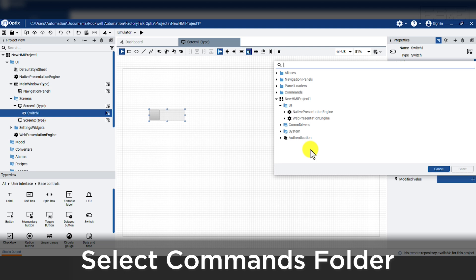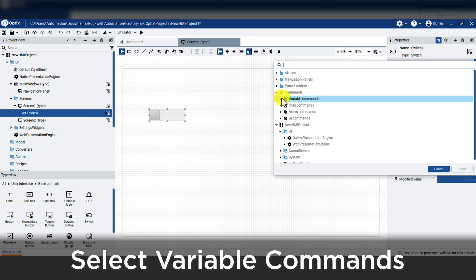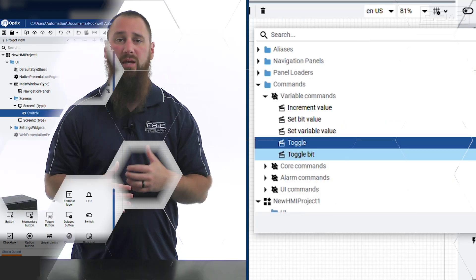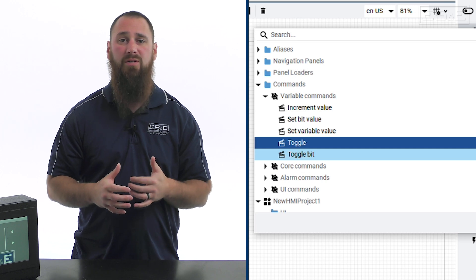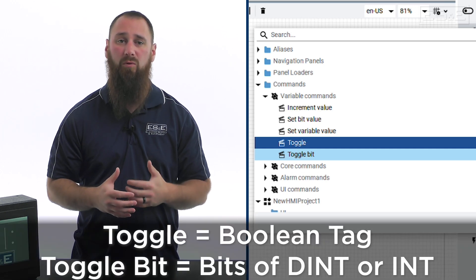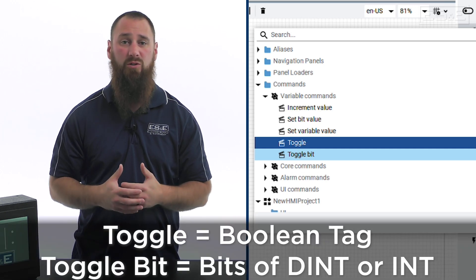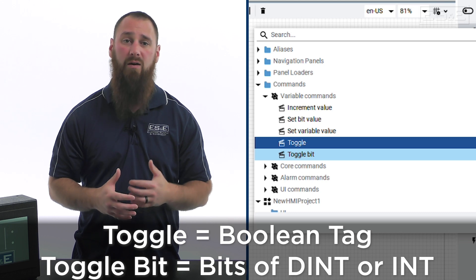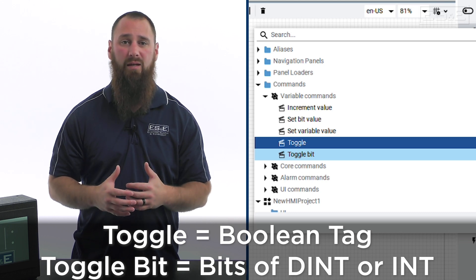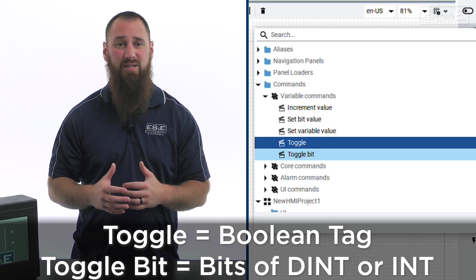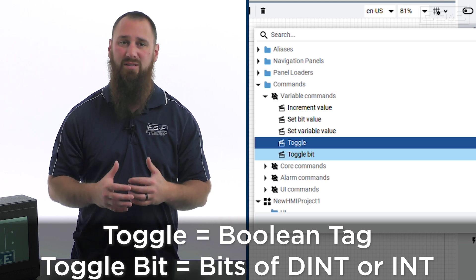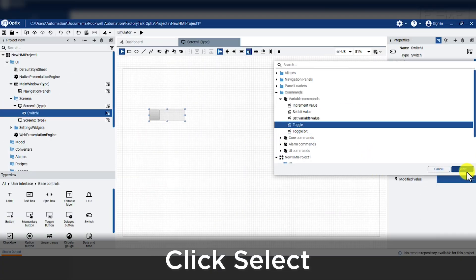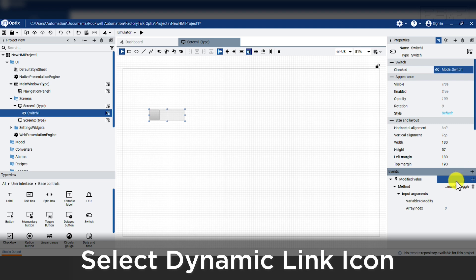Even though there is a toggle bit command, we are working with a boolean tag so we should choose toggle. Toggle bit allows you to edit individual bits of a dint or int data type. After we highlight toggle, we need to press the select and then the event is added to the switch.